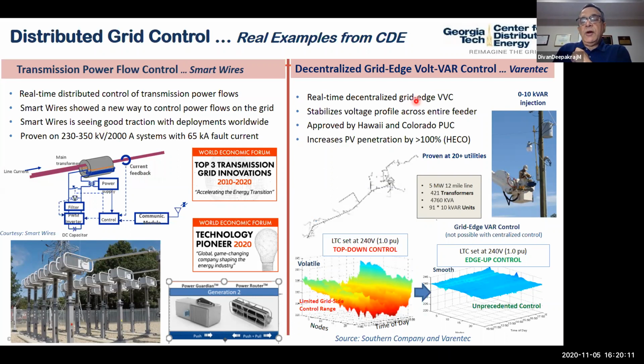On the distribution side, I started Varentec, and we developed a little volt-var control device that would go on distribution feeders. This is a 0 to 10 kVAR injection device that sits on the secondary of a distribution transformer. This is an example from a Southern Company feeder, a 5 megawatt feeder, where we had 91 of these devices installed. This shows the voltage profile at these 91 points before the devices were deployed, and this shows the voltage profile after the devices were deployed.